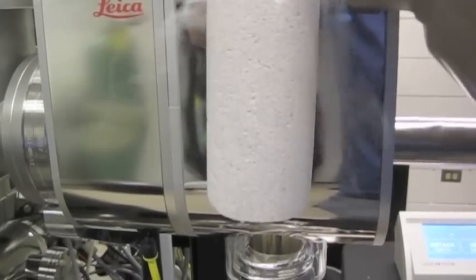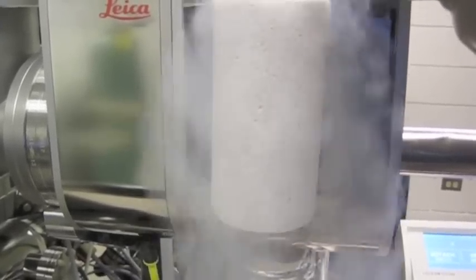We then plunge freeze in liquid ethane and transfer quickly to liquid nitrogen, where the sample is shielded from ambient atmosphere and frost contamination. We then pull the sample into a transfer arm, which is also cooled using liquid nitrogen. It is then attached to the LEAP and moved into the analysis chamber.